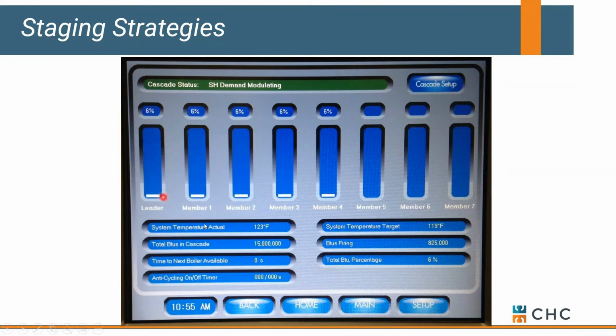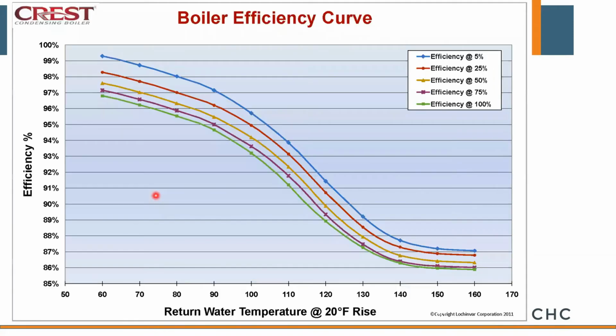So in our case, we've got 5 boilers, potential for 15 million BTUs worth of heat, but all told, they're putting out 825 by running each boiler at minimum firing rate, or in this case, 6%. And the goal is to maximize efficiencies, and you do that at low fire, okay? So this all comes down to coordination, minimum flow rate through the boilers, and control sequence. Boilers are smart enough to do this, whether you deal with a building management system or you let the boiler do its own control. Typically, the boilers are smart enough to stage based on efficiency. So again, just remember, fancy heat exchanger, the less heat we put into it, the more efficient it becomes.